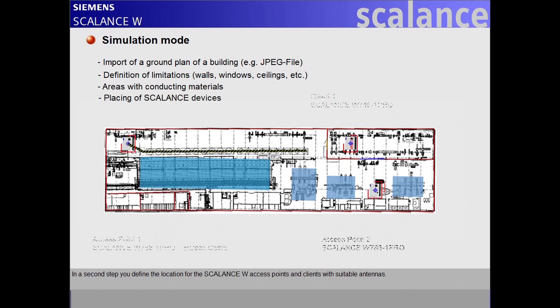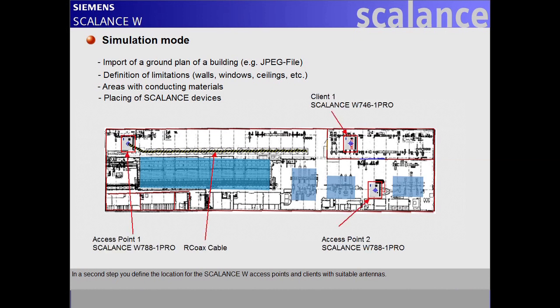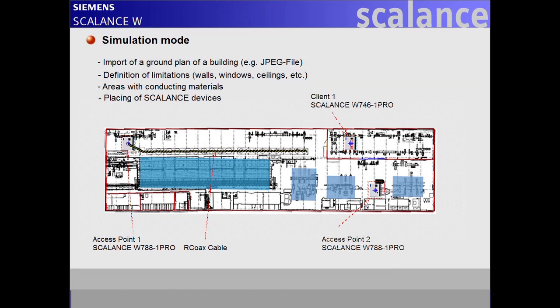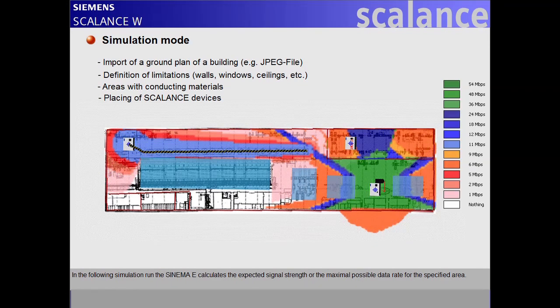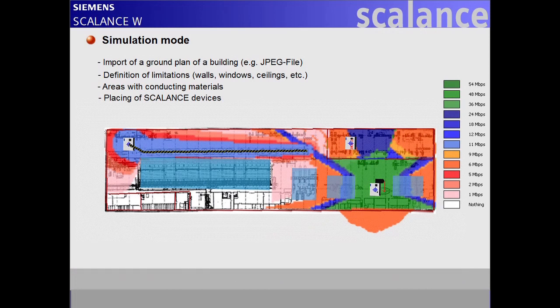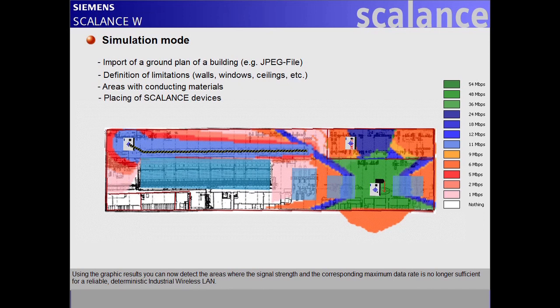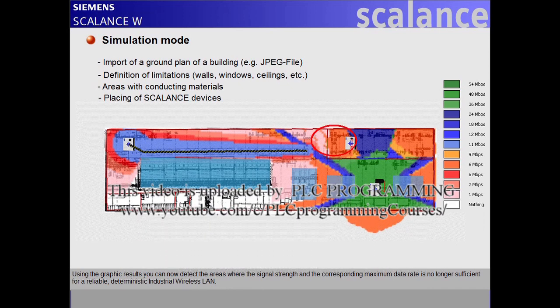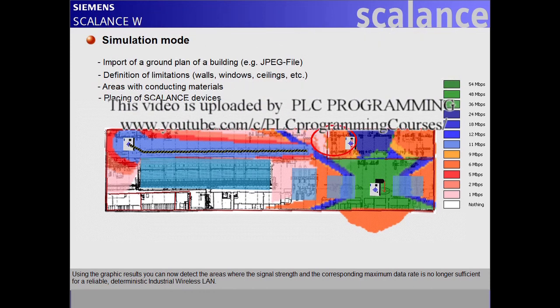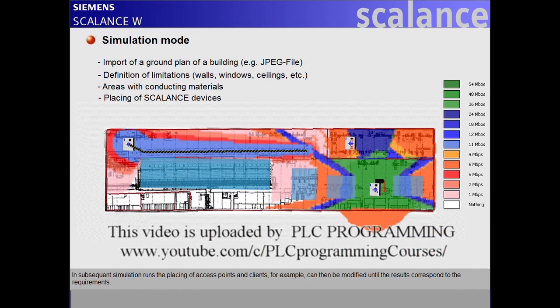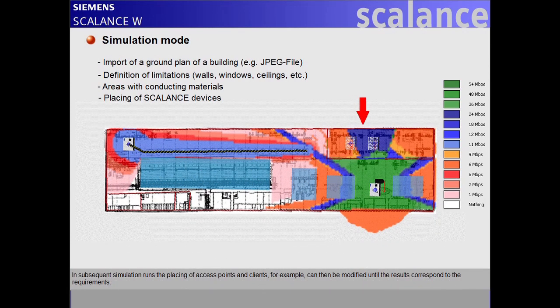In a second step, you define the location for the Scalance W access points and clients with suitable antennas. In the following simulation run, SINEMA E calculates the expected signal strength or the maximal possible data rate for the specified area. Using the graphic results, you can now detect the areas where the signal strength and the corresponding maximum data rate is no longer sufficient for a reliable deterministic industrial wireless LAN. In subsequent simulation runs, the placing of access points and clients can then be modified until the results correspond to the requirements.